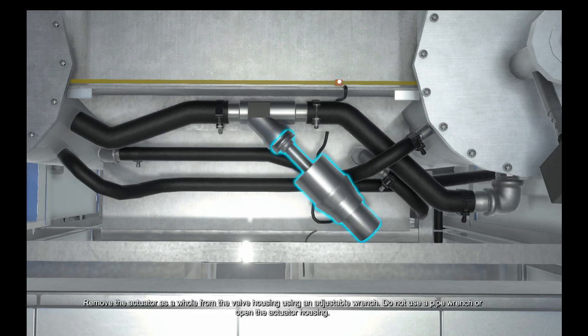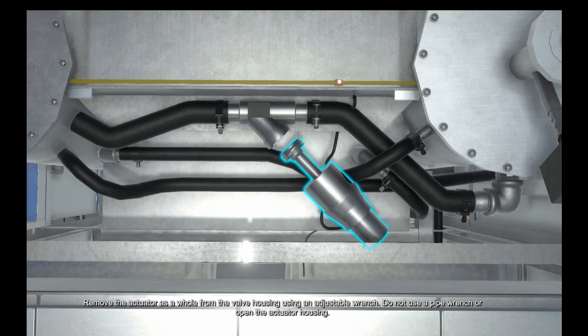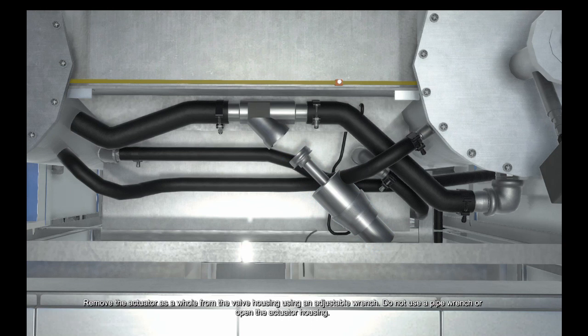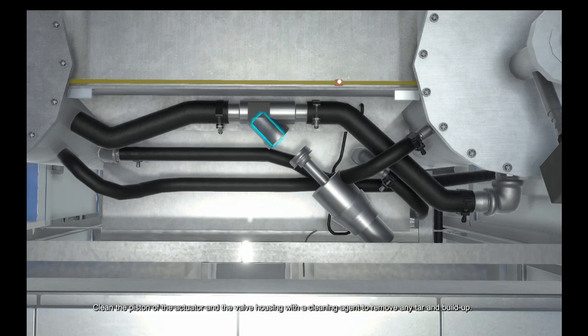Remove the actuator as a whole from the valve housing using an adjustable wrench. Do not use a pipe wrench or open the actuator housing. Clean the piston of the actuator and the valve housing with a cleaning agent to remove any tar and buildup.